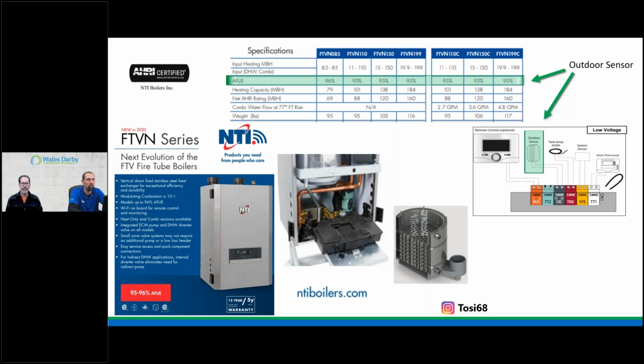We need to start understanding that word, change. I need to change the approach. I need to understand the envelope of the building. I need to understand what the heat loss requirements are, and then I apply my systems. Now, think about this. I'm not saying we can't be higher than the most efficient state. If it starts at 130, well, if I can design my design day for 130, that's such a small portion of our heating seasons. So imagine now it's somewhere in the 30s.